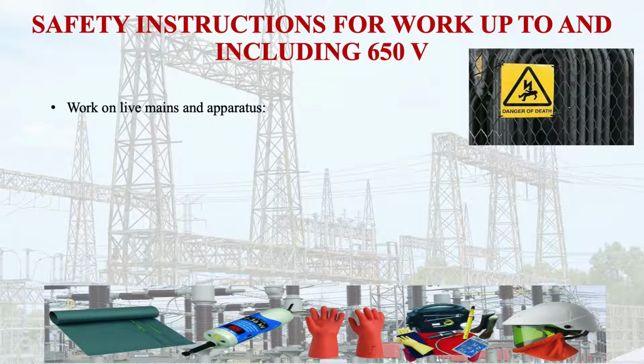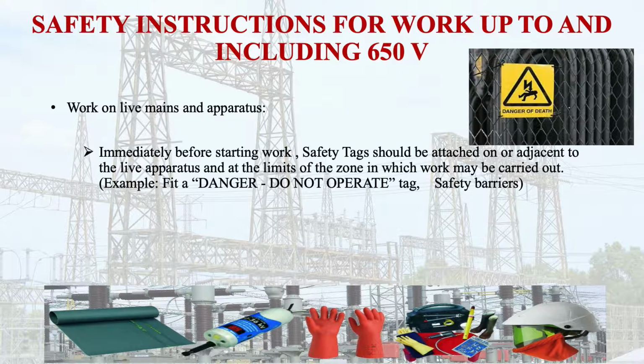Work on live mains and apparatus means that immediately before starting the work, safety tags should be attached on or adjacent to the live apparatus and at the limits of the zone in which the work may be carried out. That means it is necessary to attach the safety tags before starting the work. There may be any kind of danger tag, such as a do not operate tag, or any other.